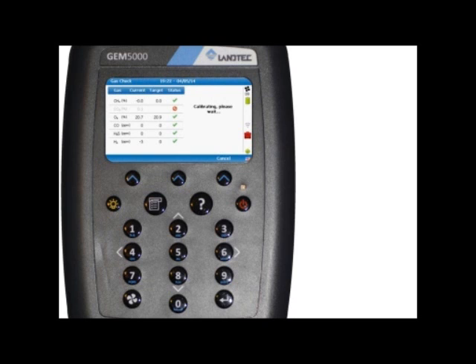The unit is now calibrating, and this should take a few seconds. Then a calibration successful message will appear indicating all channels have been properly calibrated. Note that at this point the values are not being stored to the memory, so if you're running ambient air, do not turn off the pump at this time. And if you're using a calibration gas bottle, do not turn off the gas at this point until the calibration values have been saved. How do we do that? To save the results, press the right soft key to select exit.